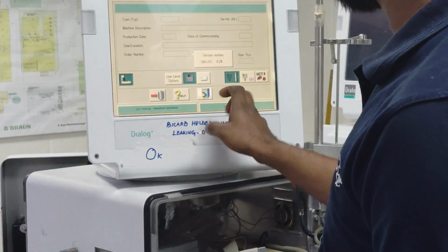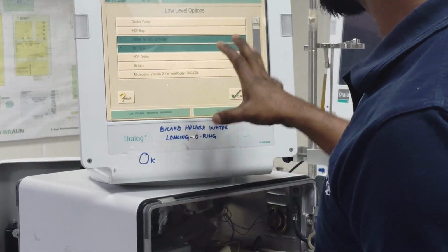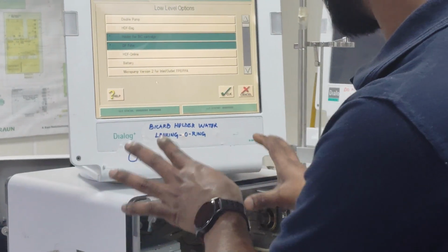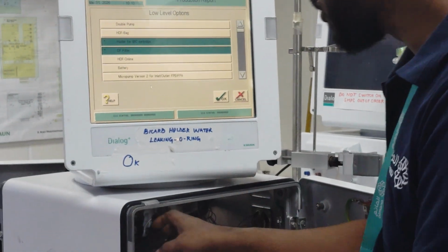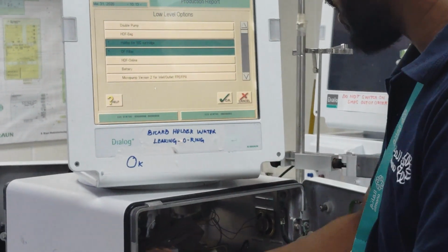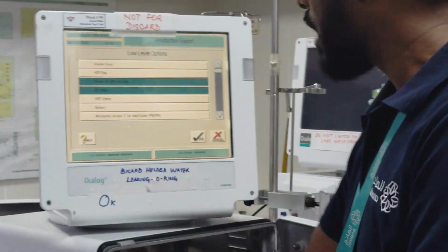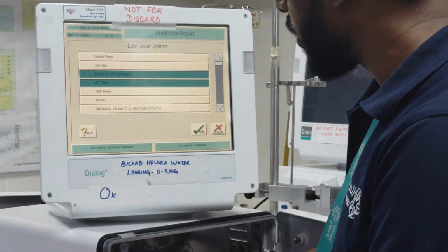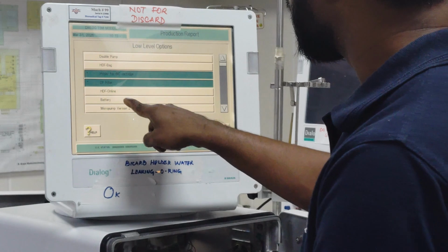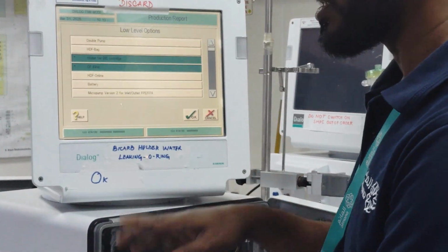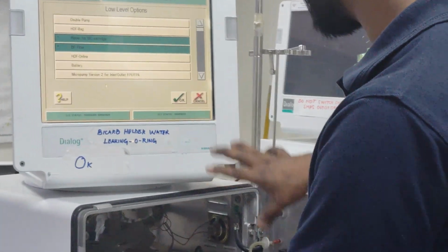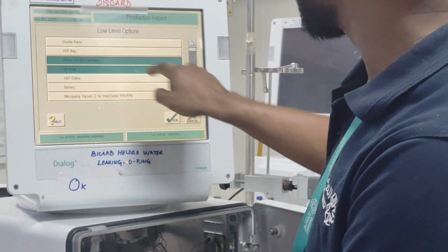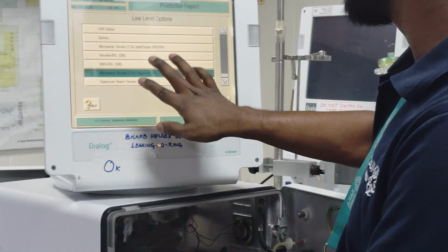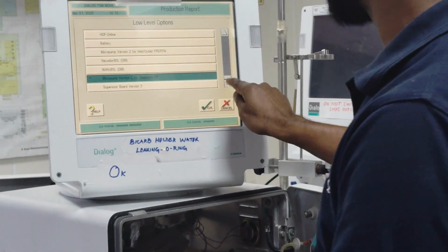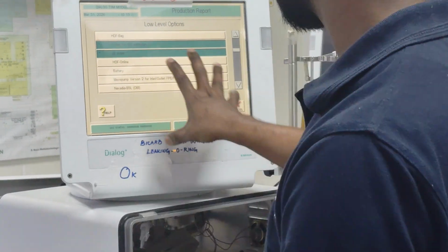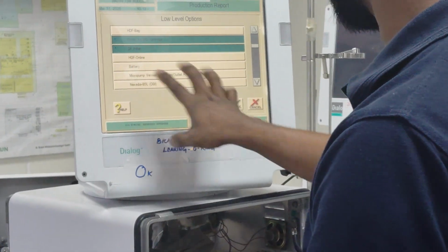There is something we call the production report. This production report depends on the device configuration. Like, if we have installed the floppy drive, we have to enable it from here. If we disable it, it will not be active. If we have used the BP module, we have to enable it from here, otherwise it will not be active. If a battery is used, you have to enable it from here, otherwise it will not be active. All the devices that are in use have to be enabled from here. If you disable one, it will not come up in the machine, and it will raise an alarm. So whatever things they are using are already enabled over here.